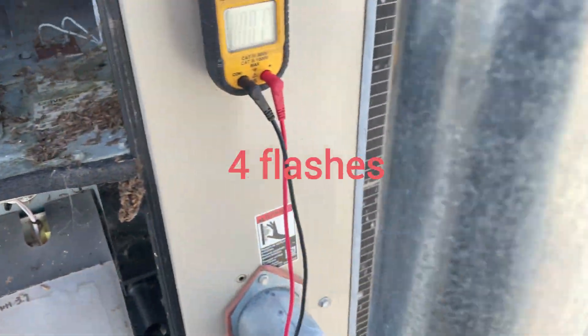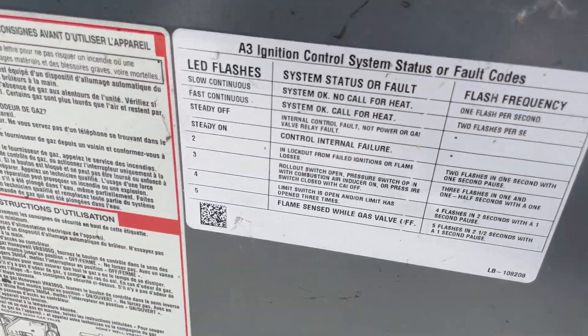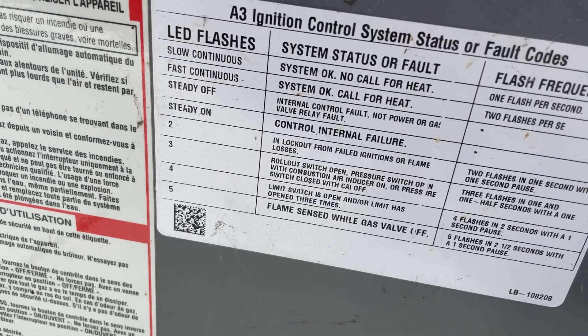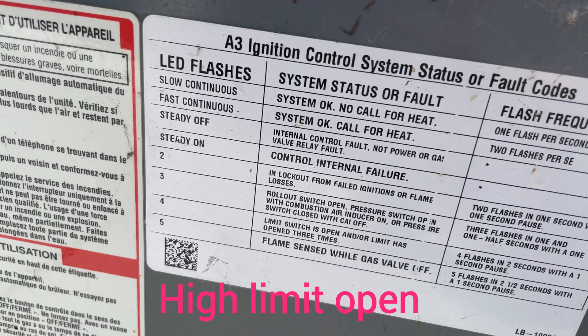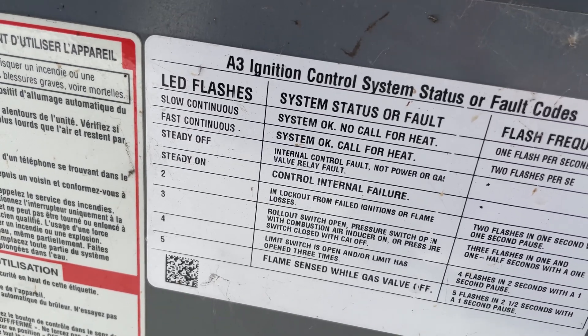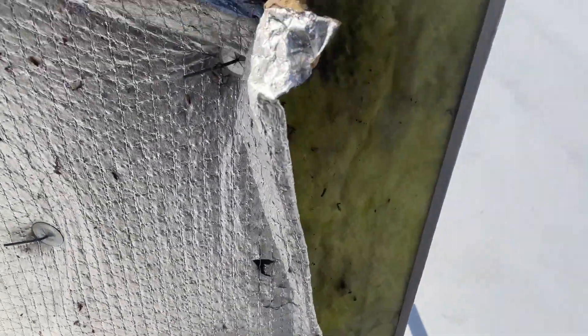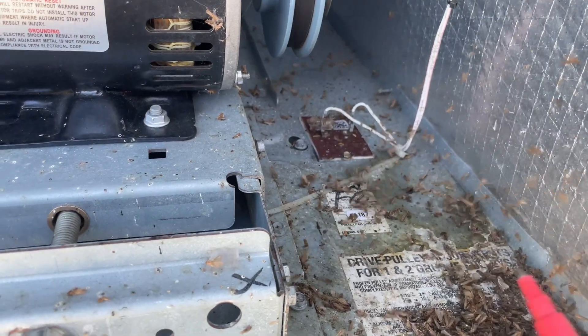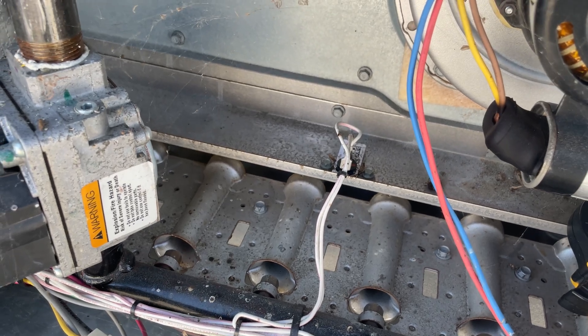4 flashes — and here is the list of error codes. 5 flashes means high limit open: the limit switch is open and the high limit has opened 3 times. I already checked the rollout switch and it is closed.